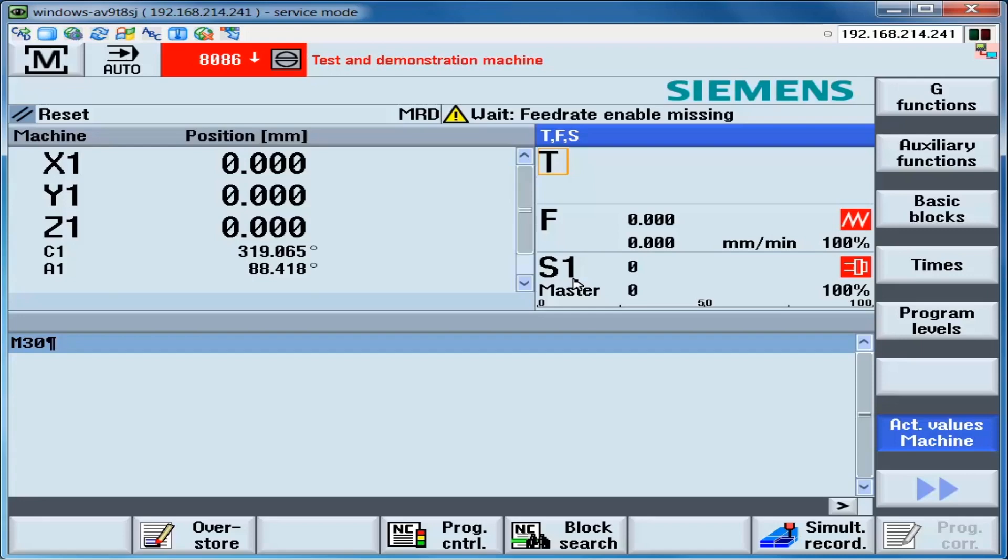This video demonstrates how to use P1990 to set the value in P431 in a common case where a third-party spindle has been repaired and is to be put back into operation. Normally, the encoder is removed or replaced during the repair process and needs to be re-synchronized. The prerequisites are the drive must be in the disabled state, the motor to drive connections must have previously been checked and verified, the encoder polarity must have been checked and verified, and the control must be in the jog mode.